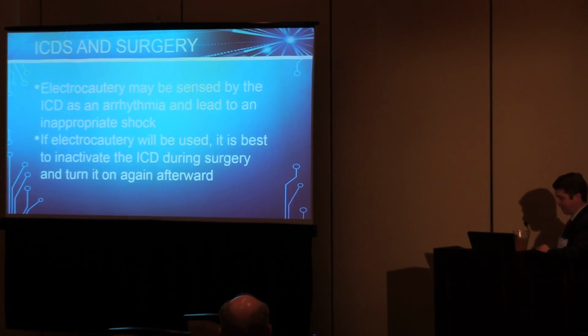The other thing, if that's not available, or surgery is emergent, is to use a magnet. Again, the idea of taking a magnet over the device will not inhibit the pacing, but will inhibit the tachytherapies while the magnet's in place. And then after removing the magnet, everything should go back to normal.